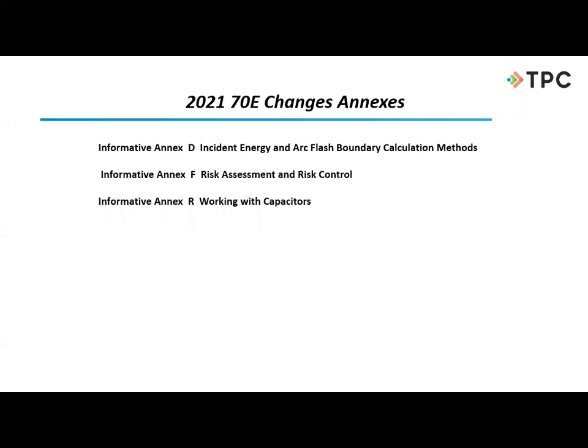They did play with some of the annexes also. Annex D was changed a bit because the IEEE 1584 software changed and has some great new formulas in there, so they wanted to reflect that a little bit. They're not going to actually show us those formulas because they're pretty complicated, but they do address that change from IEEE. Risk assessment and risk control was expanded extensively in Annex F. And then, of course, we have a new annex, Annex R, working with capacitors.